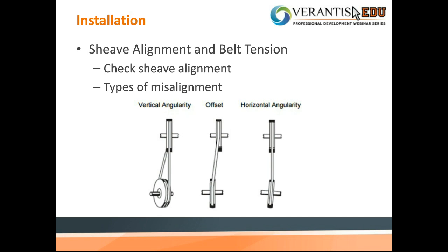So, sheave alignment and belt tension. These are very important as well. Typically the OEM is going to go through this process, and everything should be checked out by the time it ships out of the plant. Most OEMs test run all their fans to make sure everything is in proper working condition. But stuff does happen during shipment. Stuff happens during installation. It's definitely wise to check alignment before you do any startup.